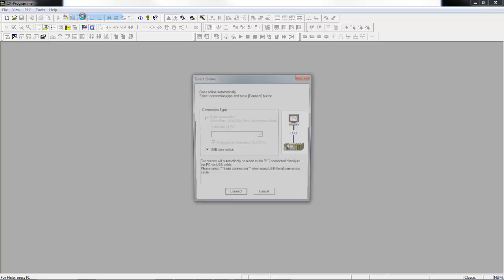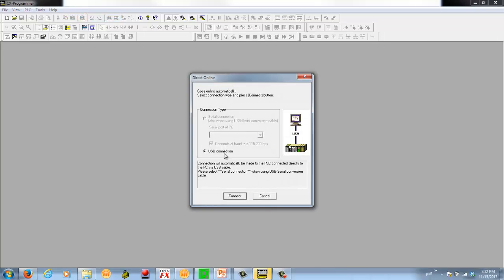So here we are in CX Programmer and the first thing we want to do is connect to the PLC. There's two methods for doing that and I'm going to show you the auto online method first. This is normally used if you don't have a project open already. So I'm going to go to the PLC menu, auto online, and I'm going to select direct online. That's for serial or USB connections. The other two options are for Ethernet. I don't actually have a serial port on this computer, so USB is the only option, and I click connect.